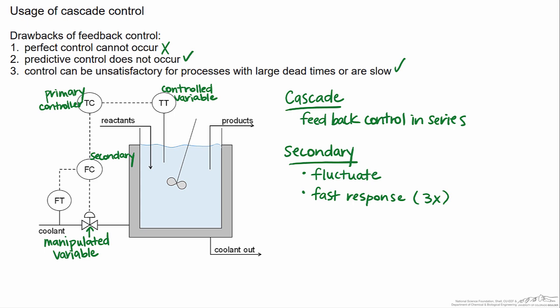So what we'll do here is kind of talk about the loop in a bit more detail. If we see a deviation to the temperature, the controlled variable, the temperature inside the reactor, the temperature controller is going to send a signal to the flow controller saying I need more or less coolant. So in other words what this is really doing is this signal here sent from the temperature controller to the flow controller is setting a new set point for the secondary controller. So with this new set point the secondary controller can then take what the new value should be in order to get the desired temperature. Compare it to what the flow rate of the coolant actually is, take those two pieces of information together and adjust the valve. Additionally what this can also do is handle adjustments in the flow transmitter, the flow of the coolant, and make those adjustments even if the temperature has not changed. Again this is why the response is quicker than it would have been originally if we just had a pure feedback scheme where the temperature controller was directly connected to the valve.